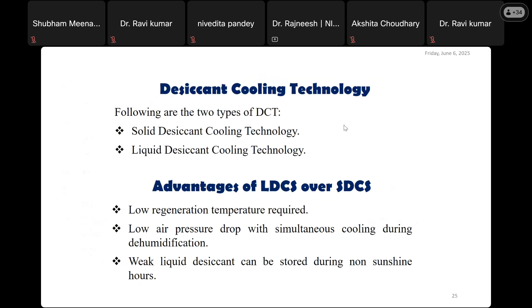Weak liquid desiccant can be stored during non-sunshine hours, so this acts as a storage medium too. A weak liquid desiccant means the moisture content is more; it has absorbed the moisture and can be stored during non-sunshine hours, then circulated again during sunshine hours so it can be regenerated and utilized.